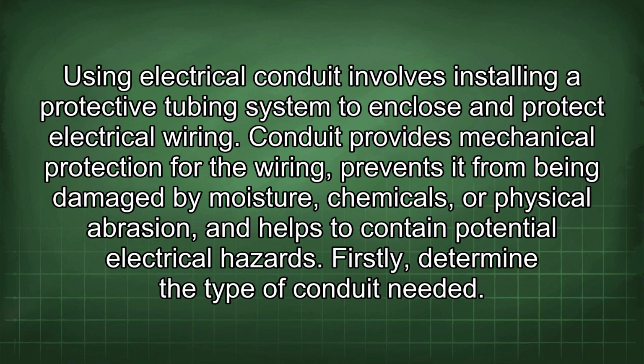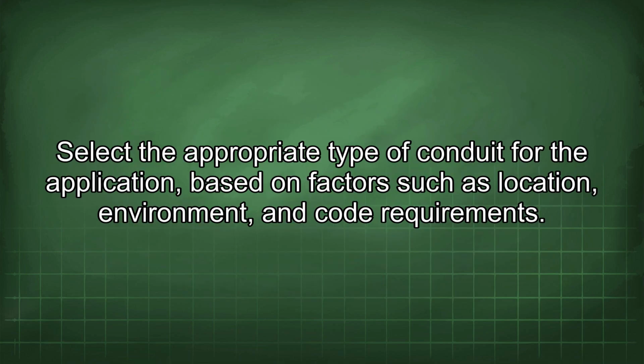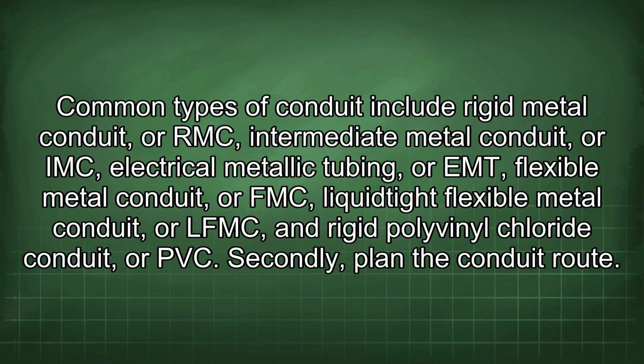Firstly, determine the type of conduit needed. Select the appropriate type of conduit for the application, based on factors such as location, environment, and code requirements. Common types of conduit include rigid metal conduit, or RMC, intermediate metal conduit, or IMC, electrical metallic tubing, or EMT, flexible metal conduit, or FMC, liquid-tight flexible metal conduit, or LFMC, and rigid polyvinyl chloride conduit, or PVC.